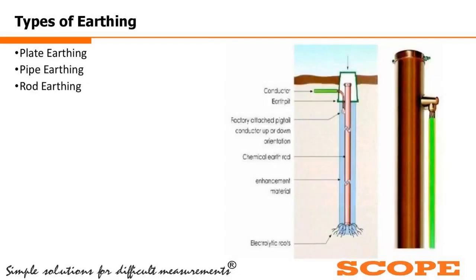So the moment we change from pipe to rod, it is called rod earthing, where the construction remains almost the same. There is the earth pit, then we put the rod inside, making a hole as desired, and from that rod we connect our equipment earthing to this system or ground.